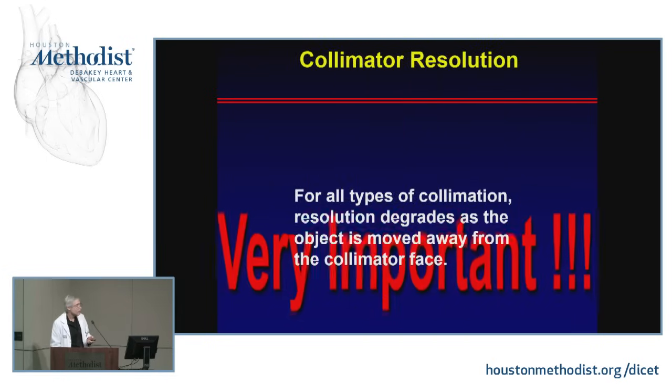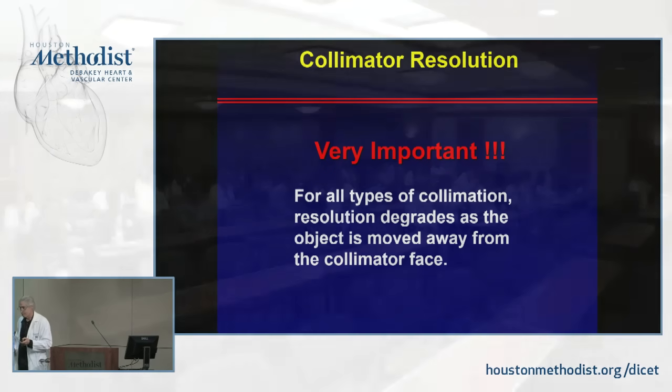Okay? So what can you adjust? You have to decide on your collimator, the physics of the machine. There are two things, at least to my knowledge, that could influence your sensitivity and your spatial accuracy. One, the type of agent you're using, and two, how close you are to the camera. Is there something else? Being close to the camera doesn't affect your sensitivity, but it does affect your spatial resolution.